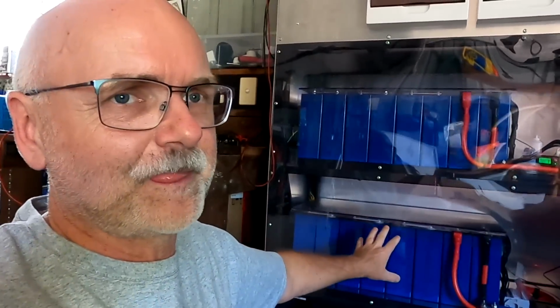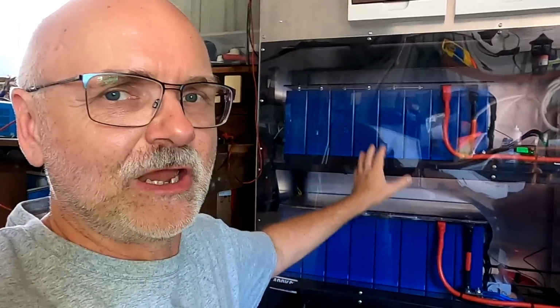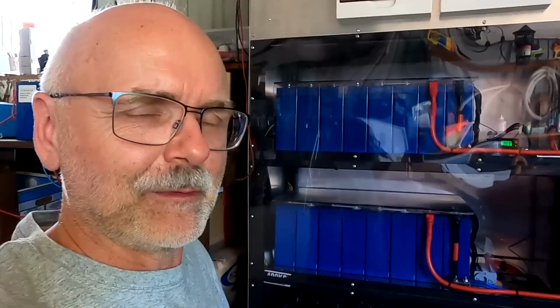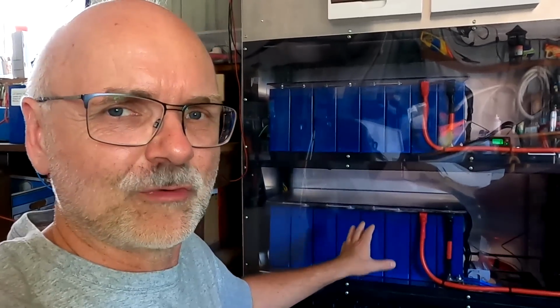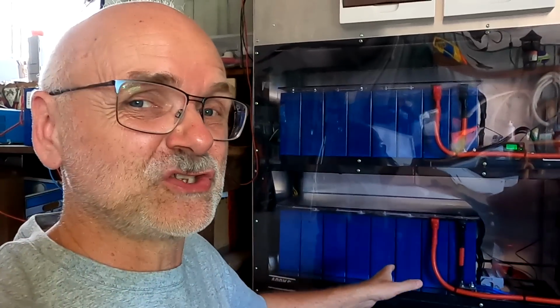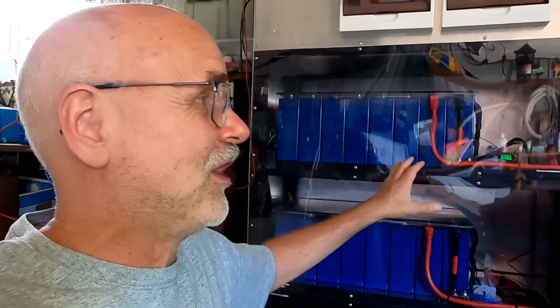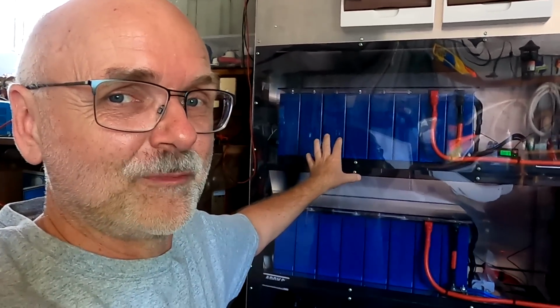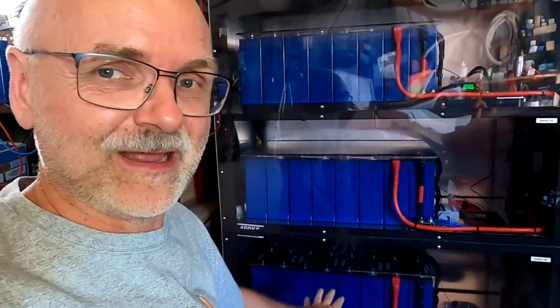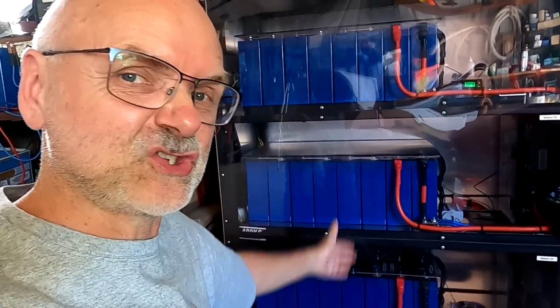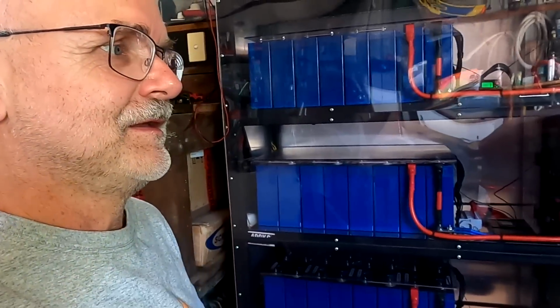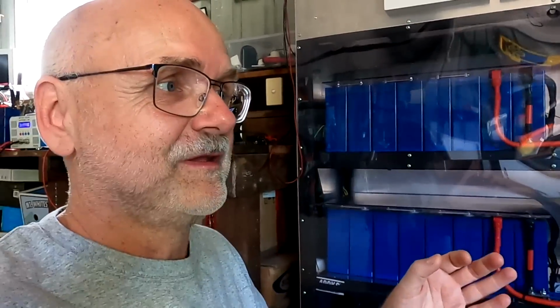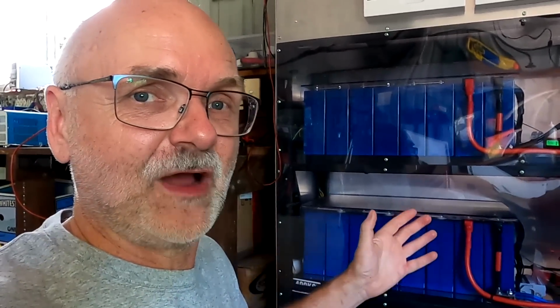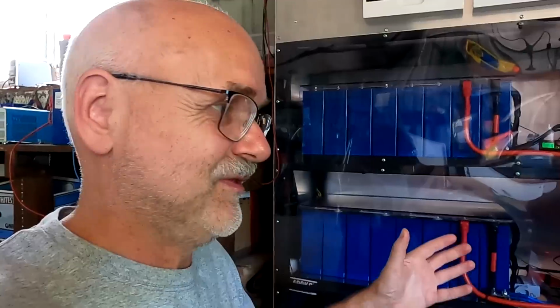This is actually not too important because we have 3 battery banks and they're sharing the load. I will never have 100 amps going through a battery bank under normal conditions unless I do one of these tests, or I need to turn off one of the battery banks, but then still we have another battery bank and the current will be shared between these 2 then. And 100 amps is 5 kilowatts.